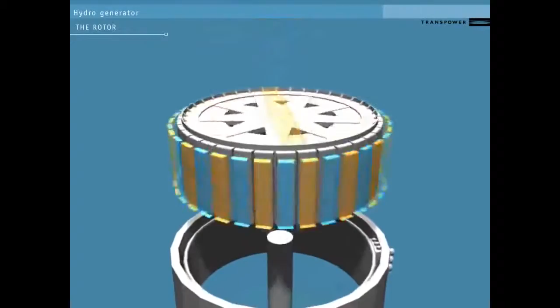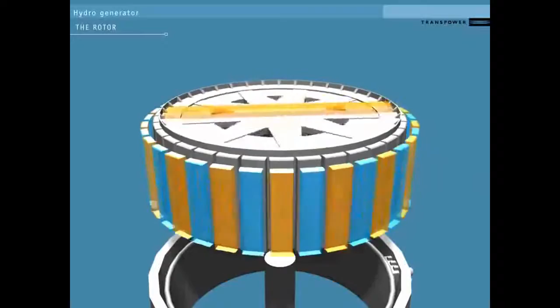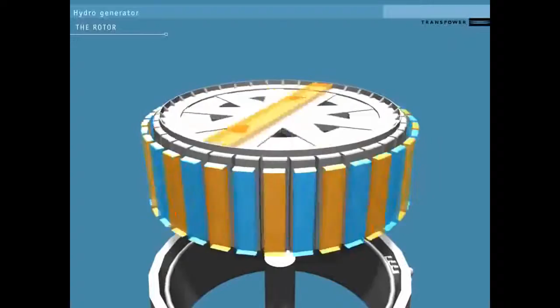On the rotor are a number of electromagnets, powered by the DC current from the exciter. If these are switched off, the turbine will be able to spin without generating any electricity. The magnet's poles on the outside of the rotor create a separate rotating magnetic field for each magnet. The magnets are lined up so that adjacent poles always have opposite fields to each other: north, south, north, south.